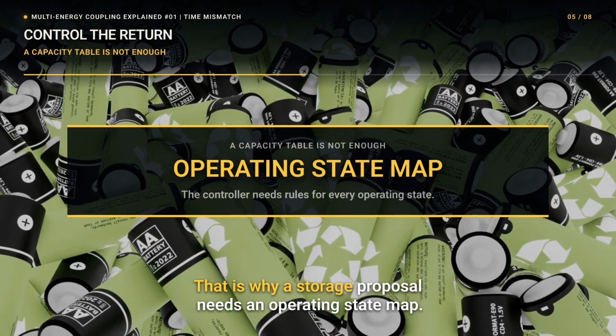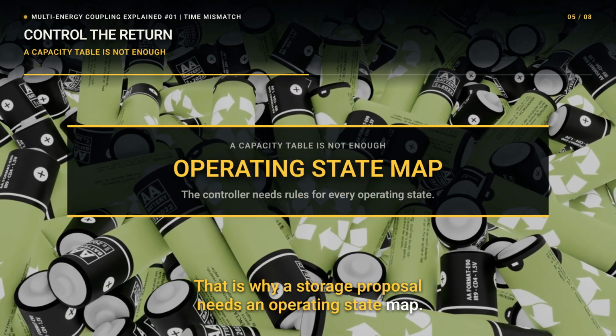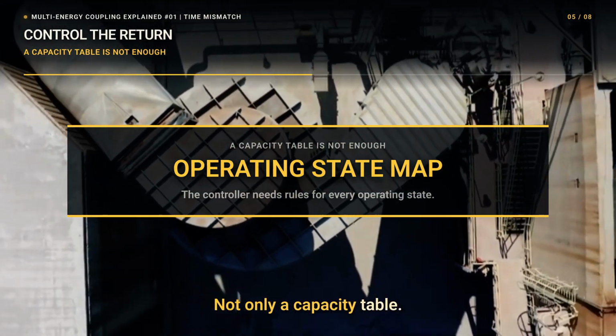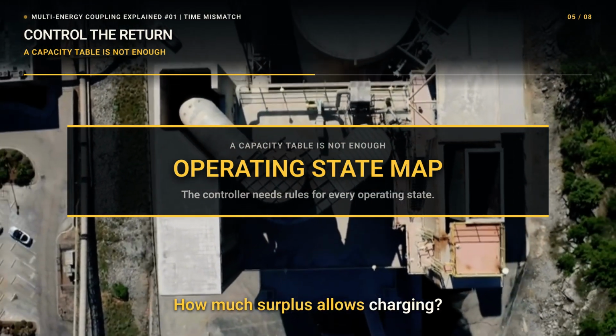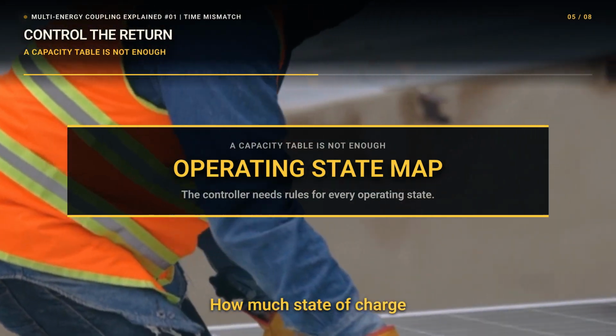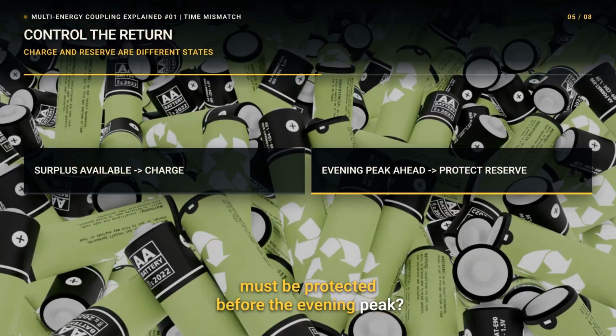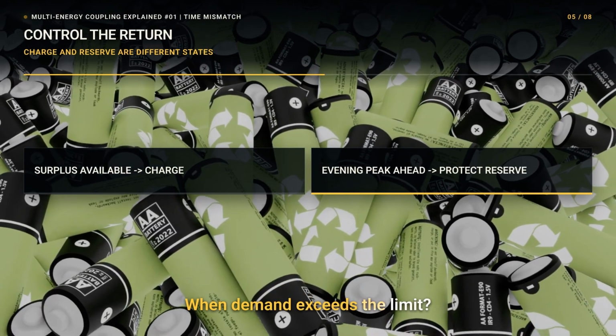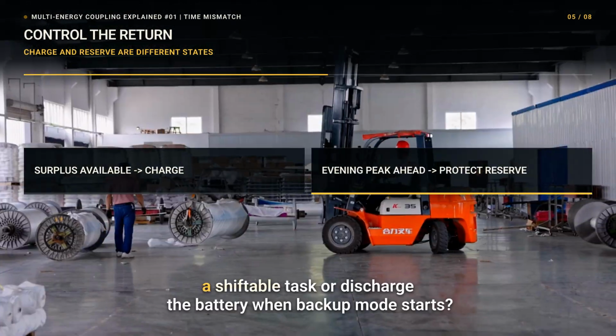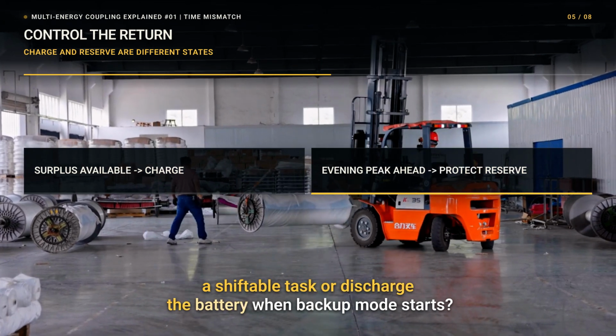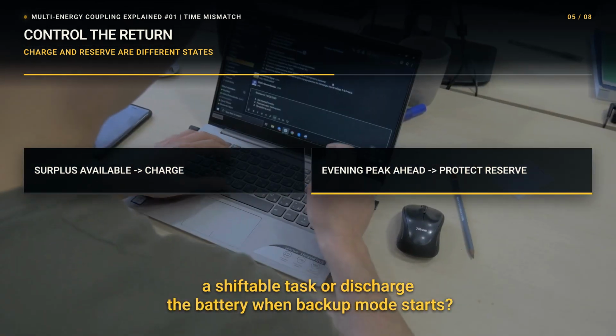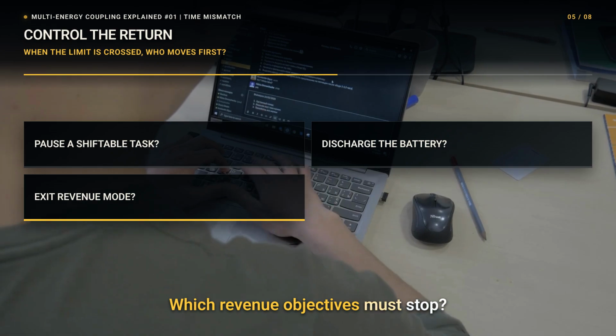That is why a storage proposal needs an operating state map, not only a capacity table: how much surplus allows charging, how much state of charge must be protected before the evening peak. When demand exceeds the limit, should the controller pause a shiftable task or discharge the battery? When backup mode starts, which revenue objectives must stop?